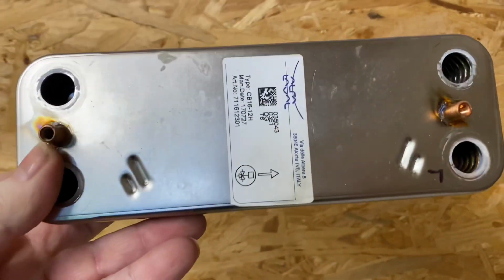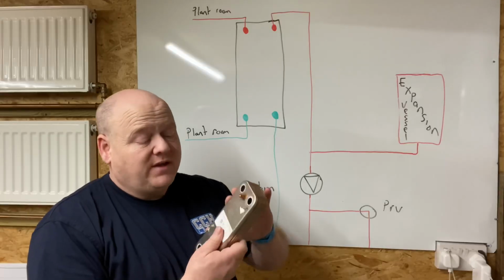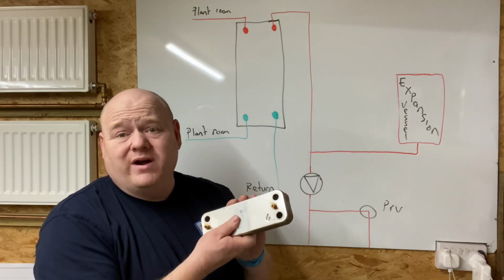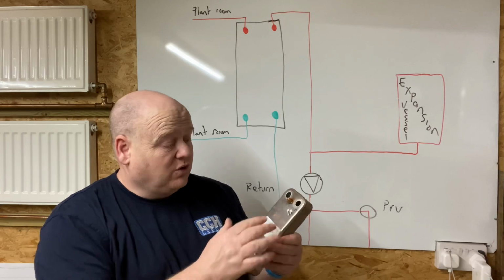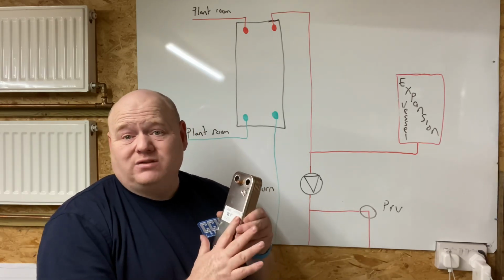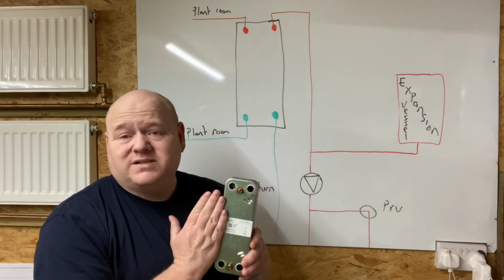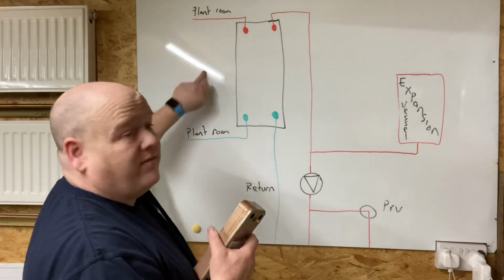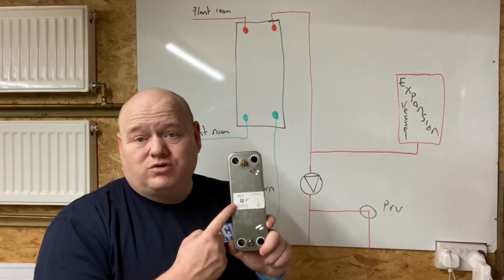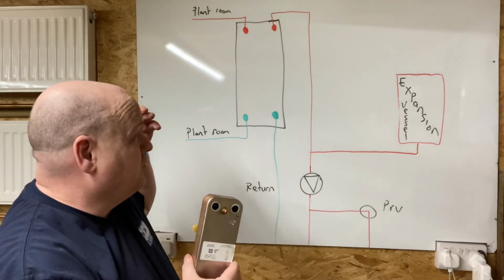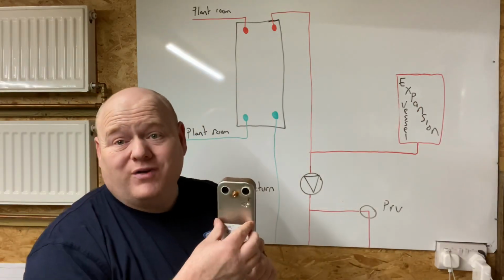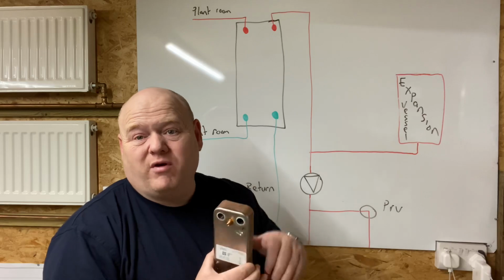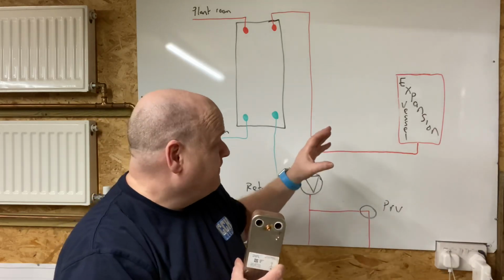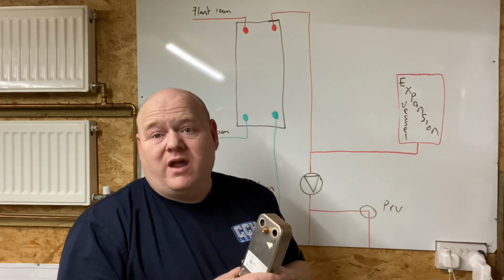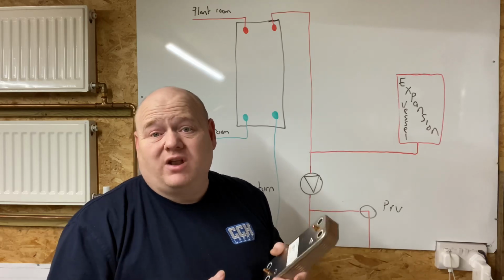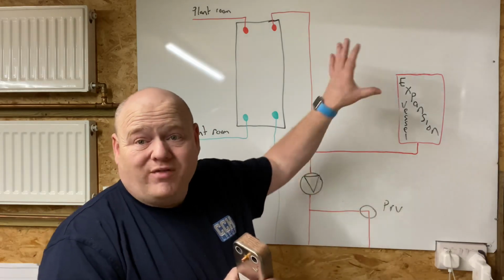Another problem could be a plate heat exchanger blocking up. If these start to get sludged up, depending on where you are in the country, they could also get scaled up as well. So the hot water side could get scaled up in some parts of the country, but the central heating side, or the plant room side, if you like, could get blocked up too. It could get blocked up on both sides, because they're both sort of system water. They're both water that's recirculating around. So on the plate that's used for the heating side, the radiators will still need protecting, like putting your inhibitors in and things like that. So that would be on that side of it.